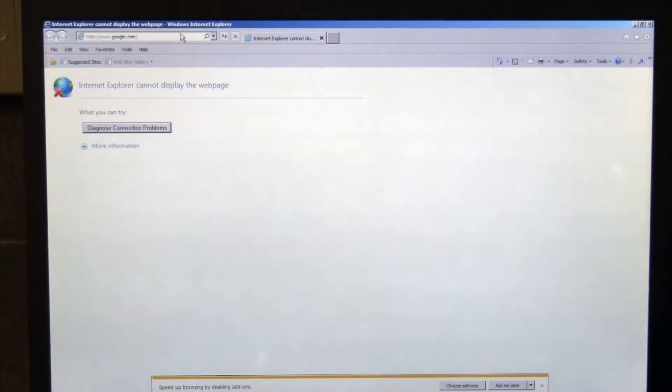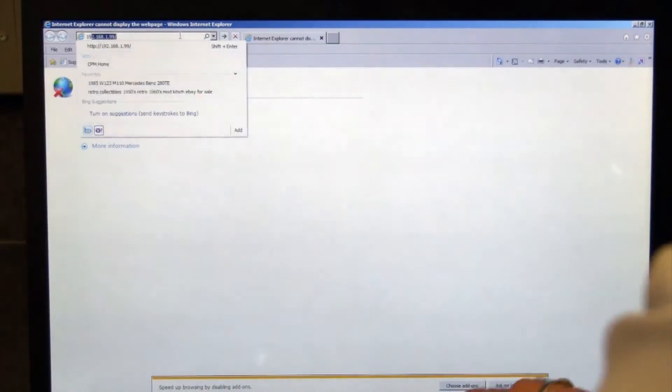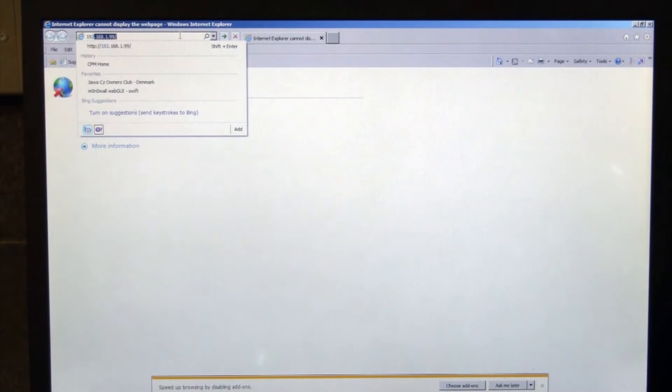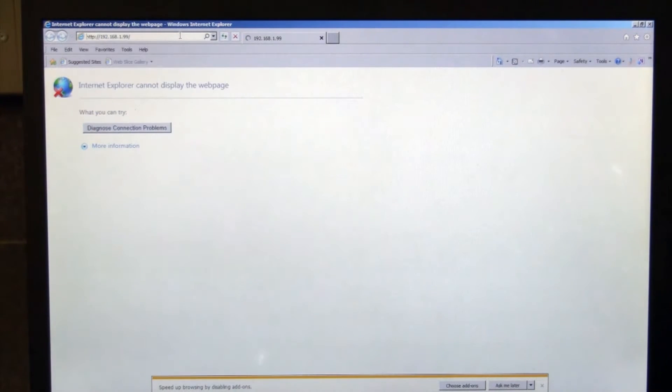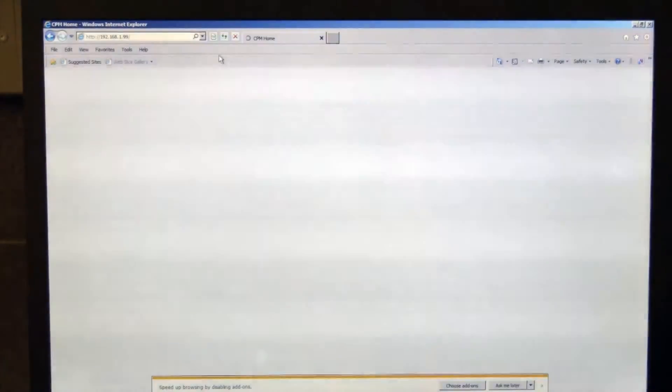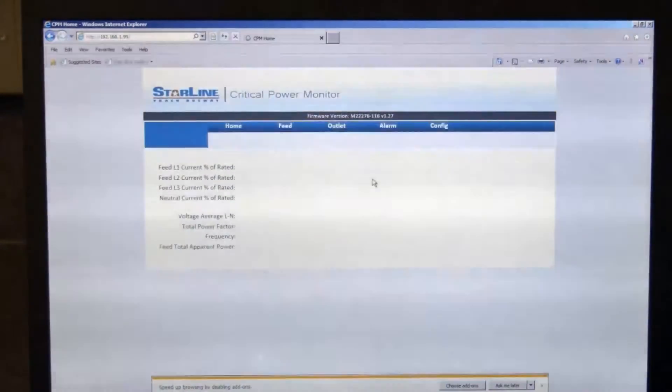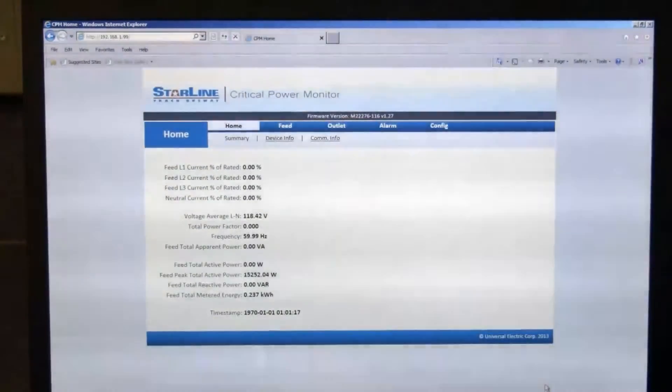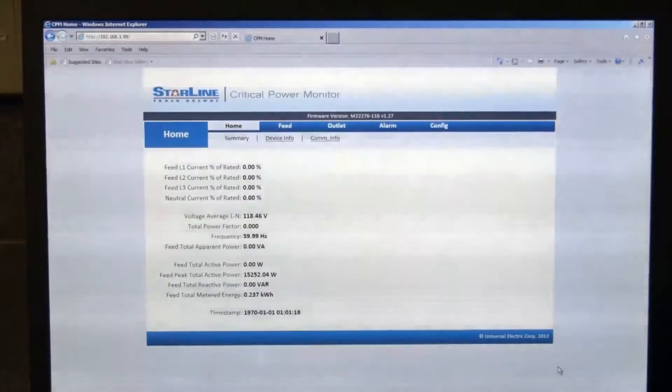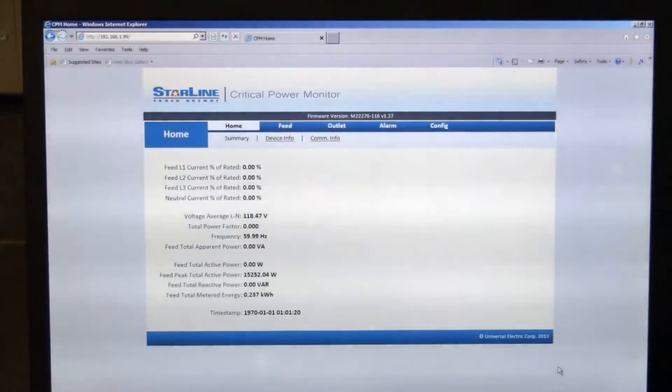All you need to do to connect to the meter once your IP address information has been changed is open your browser and type in the default IP address of the meter, which is 192.168.1.99. Hit enter, and you can see that it pulls up the integral webpage for the meter.